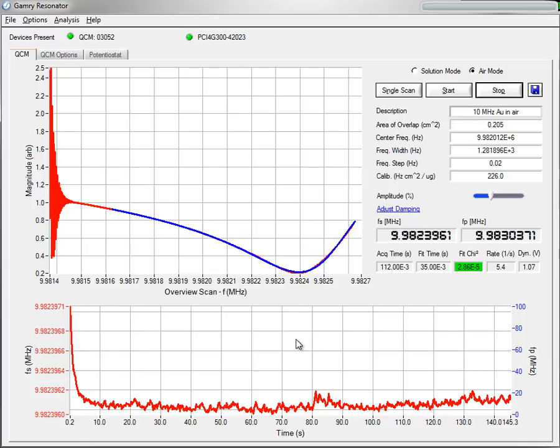One final note for resonator operating in air mode is that rapid mass changes—very, very fast mass changes—may cause resonator to lose the resonant frequencies.